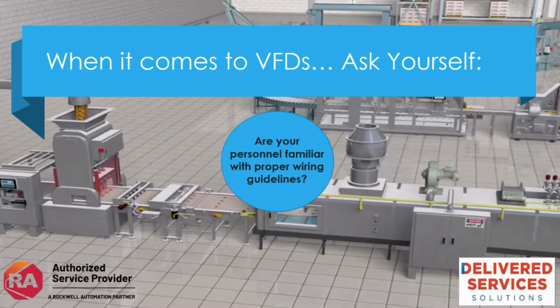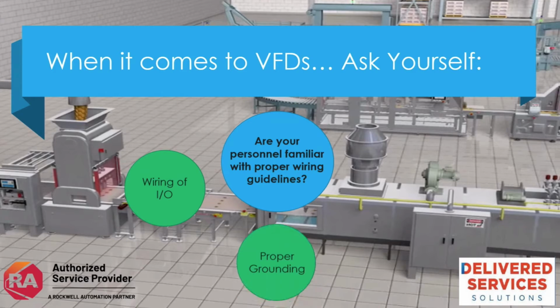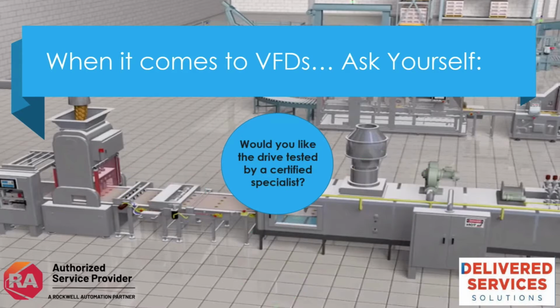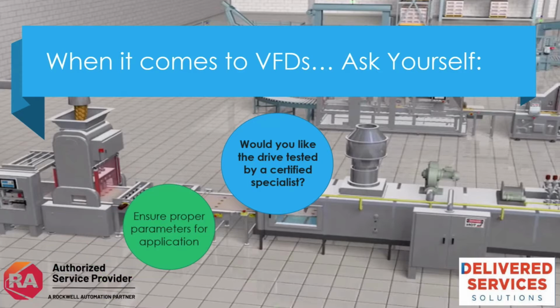When it comes to VFDs, also ask yourself, are your personnel familiar with proper wiring guidelines? Whether that's wiring of I/O, digital and analog, back to the drive, proper grounding, verifying the grounding type of your supply transformer, whether that's delta or Y, and either applying or removing power jumpers accordingly. Both of these work together to optimize longevity for the application, ensuring the longest possible life and that it's wired properly for your application. Would you like the drive tested by a certified specialist?